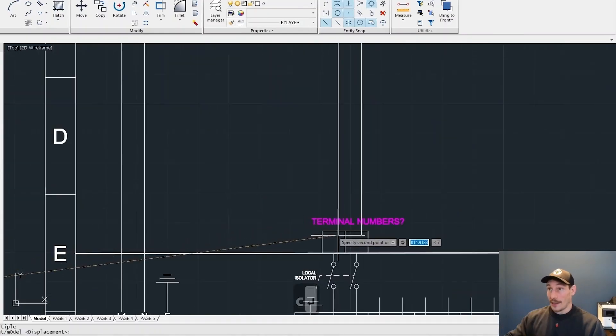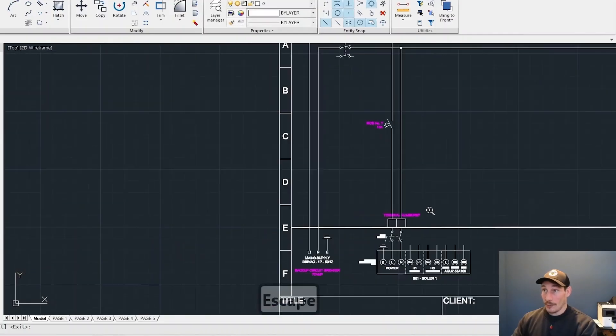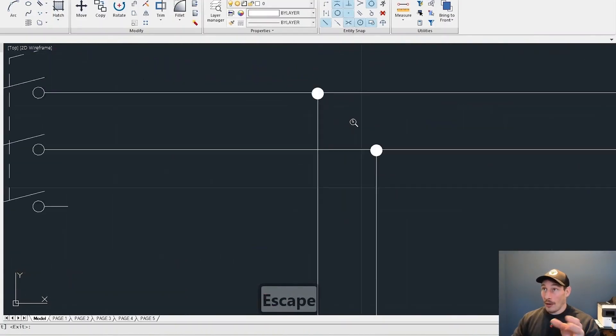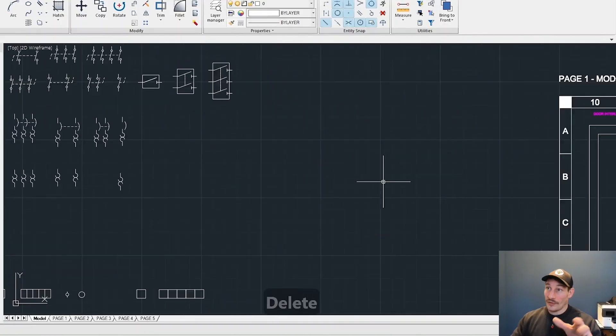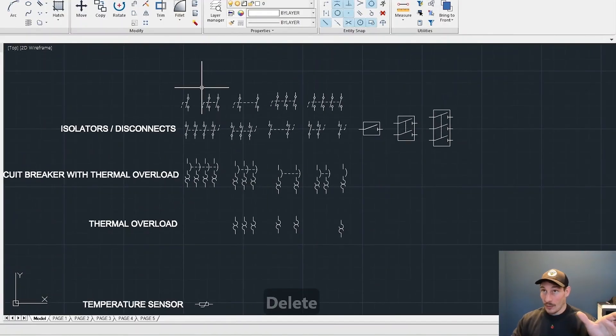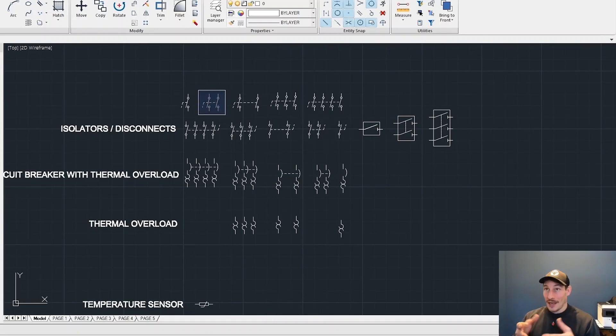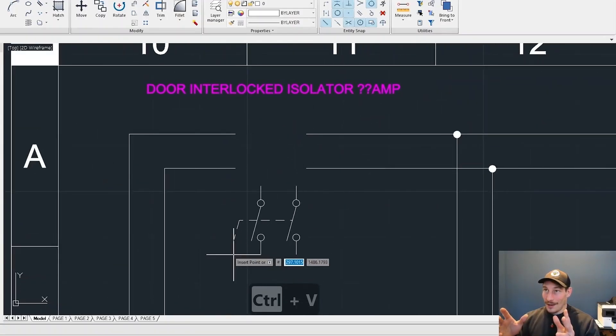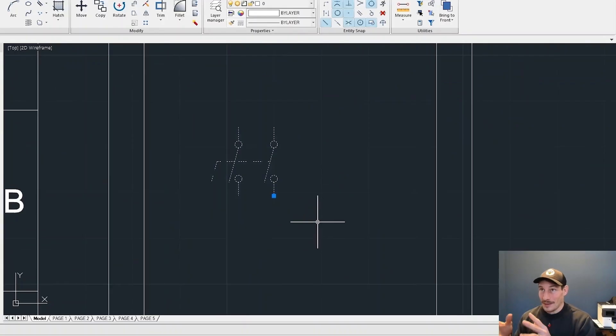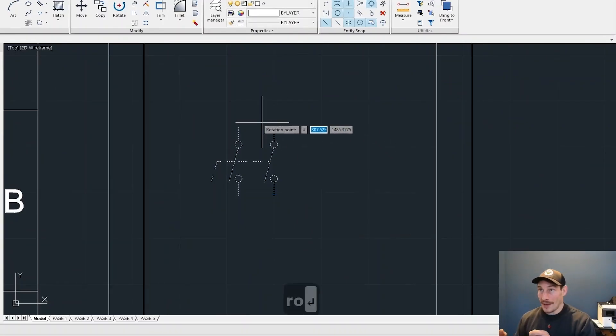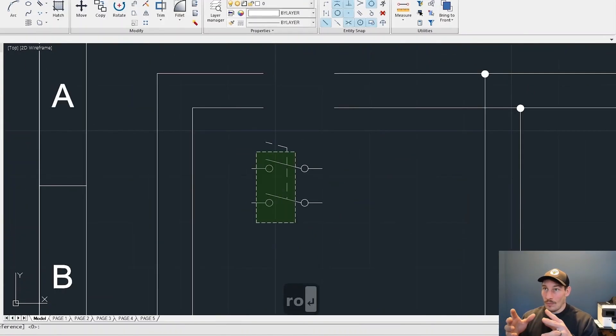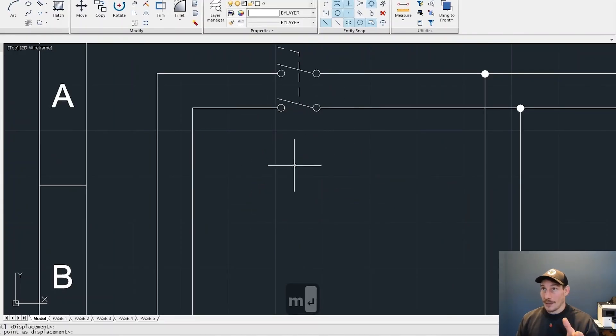Those square blocks are terminals within the panel, just above that dividing line. What you see in pink, terminal numbers, I always leave to the end once everything's done. Then I can come back and label things in order because if you start labeling things now at this early stage, it's highly likely that you're going to have forgotten something. It just makes sense with things like that. Wait till all the components are added, then put your terminal numbers, your MCB numbers.